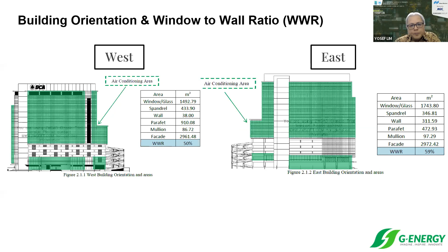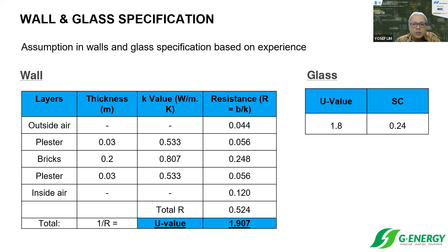So these are the areas, and these are the thermal properties used. This is the material used for the wall. For the glass, the good thing is they chose glass with good thermal properties. The U value of the glass is 1.8, which is considered quite good, and the shading coefficient is also quite low at 0.24.